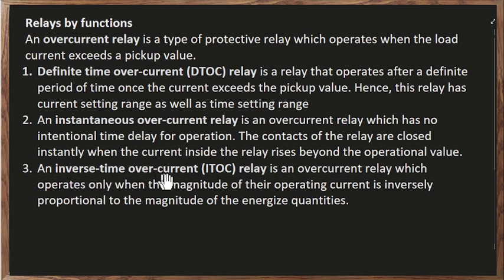An inverse time overcurrent relay is an overcurrent relay which operates only when the magnitude of the operating current is inversely proportional to the magnitude of the energized quantities. So, when we say inverse time, mas malaki yung overcurrent mo, mas mabilis siyang mag-trip. Ganun lang yung operation niya. If the value of the overcurrent is far greater, mas malaki, mas mabilis din siyang mag-trip. Kaya tinatawag siyang inverse time overcurrent.